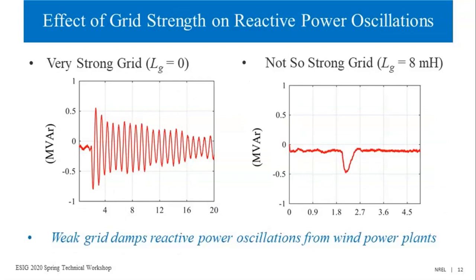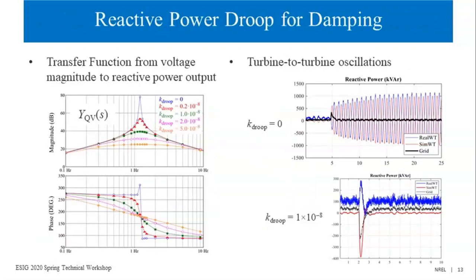Here is a comparison of the wind turbine's reactive power output for two different grid conditions that we emulated using a grid simulator. Clearly, for a not so strong grid, we see that it is damping the reactive power oscillations. The weak grid will damp reactive power oscillations from the wind plant to the grid, but it is not going to get inside the wind plant. So if there is a potential for turbine-to-turbine reactive power oscillations, the weak grid is not going to have any influence on that.